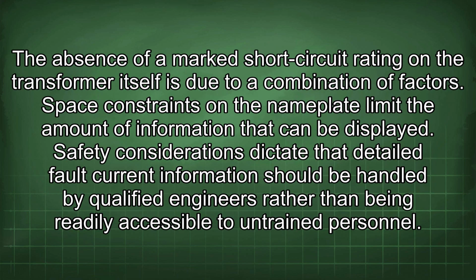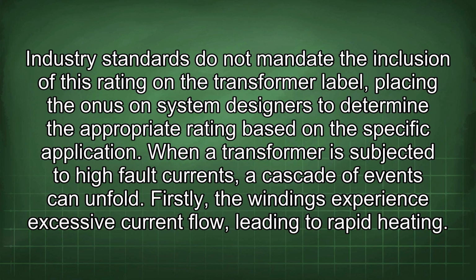The absence of a marked short circuit rating on the transformer itself is due to a combination of factors. Space constraints on the nameplate limit the amount of information that can be displayed. Safety considerations dictate that detailed fault current information should be handled by qualified engineers rather than being readily accessible to untrained personnel. Industry standards do not mandate the inclusion of this rating on the transformer label, placing the onus on system designers to determine the appropriate rating based on the specific application.